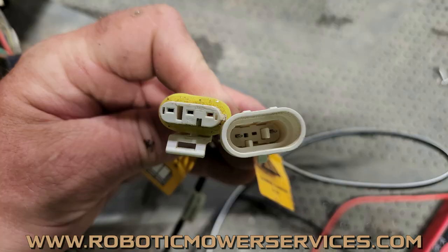...then you can unplug the low voltage cable from the charging station. Test it individually. Test from the back of your charging station to that plug in the front that goes into the circuit board, and see which component has the resistance buildup. Maybe it's both of them. It's hard to say until you actually test it.